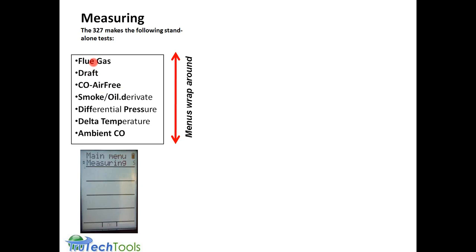The reason why there's a flue gas test, which includes a measurement of CO in the flue gas. There's also a CO air-free test, which is done separately, usually on unvented combustion appliances. And there's an ambient CO test, which is done for the background CO. They all use the same sensor. It's just more or less you're keeping track in a notebook when you store these tests away.